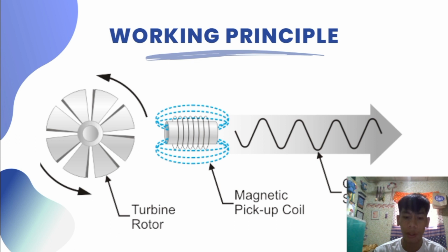Magnetic pickup coil. Inside the sensor, there is a magnetic pickup mechanism, which is often a coil or a Hall effect sensor, positioned near the rotating turbine blade. This pickup plays a critical role. As the blades spin, they pass by the magnetic pickup, inducing changes in the magnetic field and generating electrical pulses.